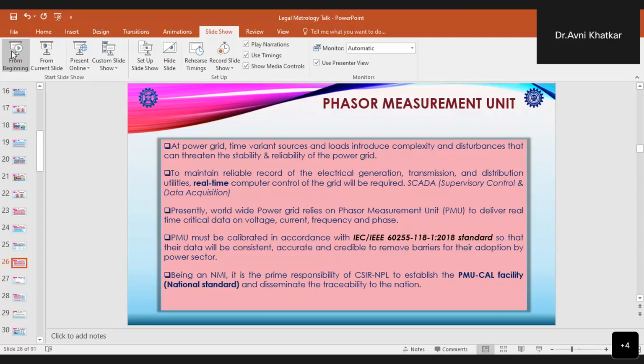So these PMUs must be calibrated in accordance with the latest standard, that is the IEEE/IEC 60255-118-1 2018 standard, so that the data which we get from these PMUs is consistent, accurate, and credible, in order to remove all the barriers to their adoption by the power sector. And being an NMI, it is the prime responsibility of CSIR NPL to establish the phasor measurement unit calibration facility, which is a national standard, and to disseminate its traceability to the nation.